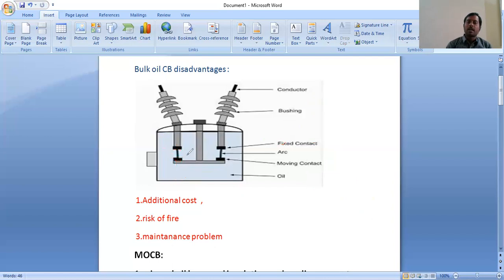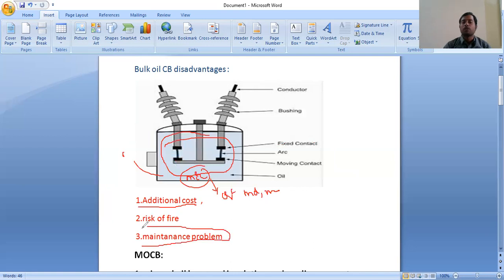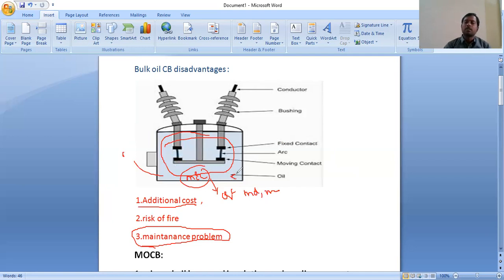As we know, the bulk oil circuit breaker has more oil, so the cost and maintenance are more. Additional cost is required and also, due to the high bulk oil, there is a chance of getting fire — so there is a huge blast that can take place by using the mineral oil. There is also a maintenance problem because regularly we need to check the performance of the circuit breaker. Due to the bulk oil, there is a huge damage potential to the entire system, so regular maintenance is required.